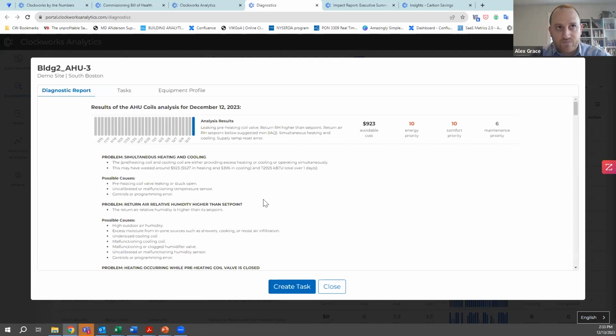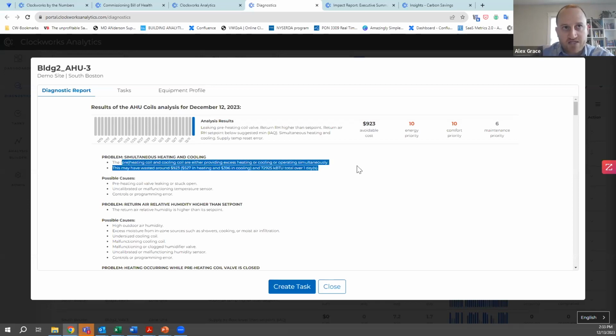And what you'll see on the screen is a list of problems and their associated possible causes. It tells us the pre-heating coil and cooling coil are providing excess heating or cooling, or operating simultaneously. This may have wasted $900 that day—actually very specifically $923, $527 from the heating side, $396 from the cooling side, total number of KBTU. So again, what's the relative importance here?